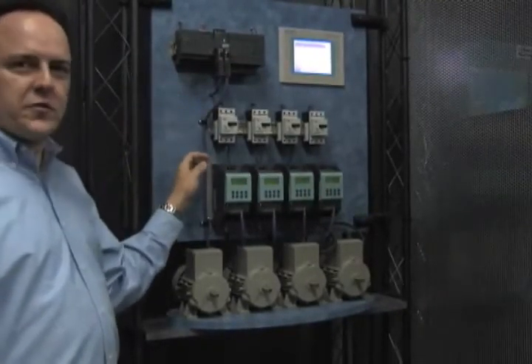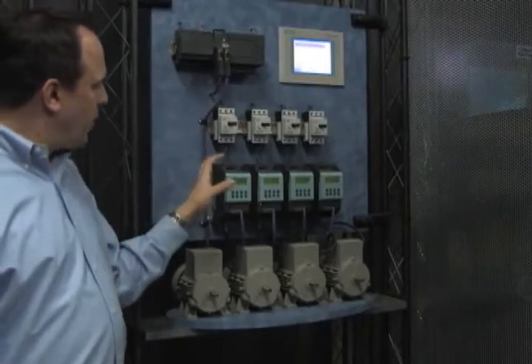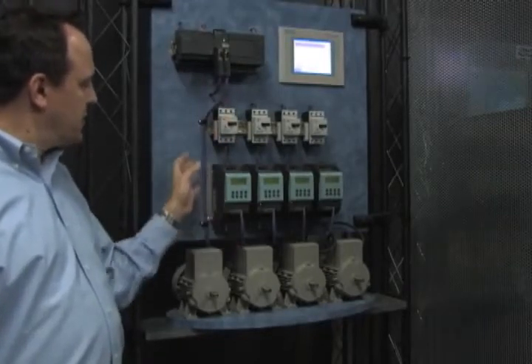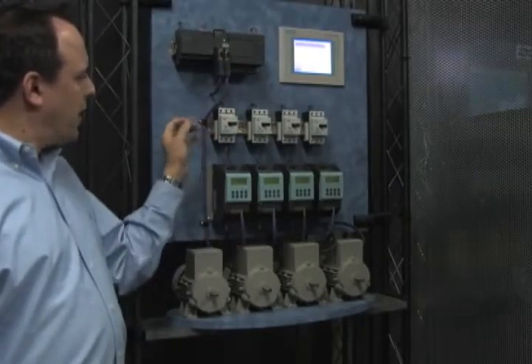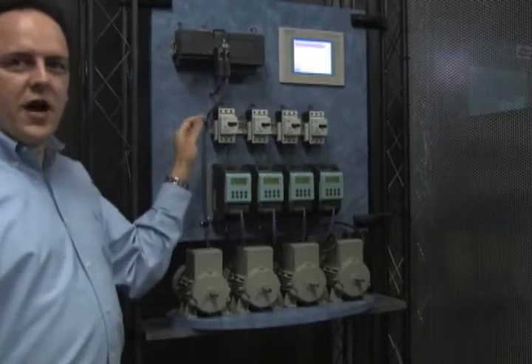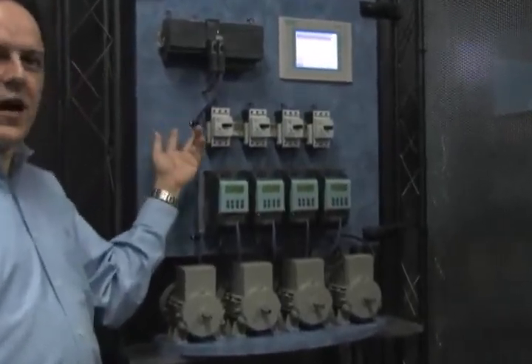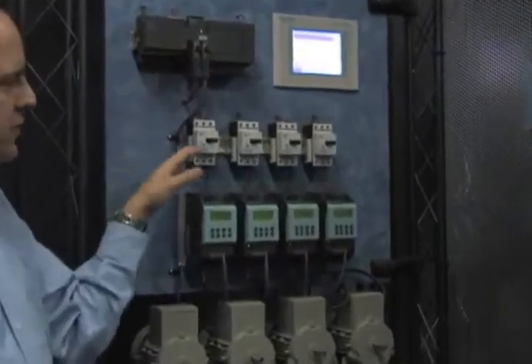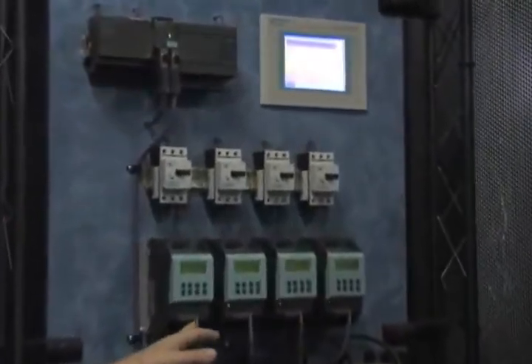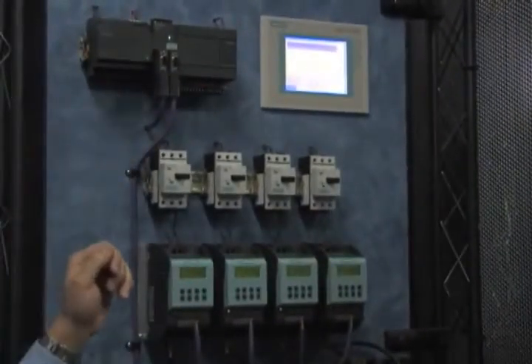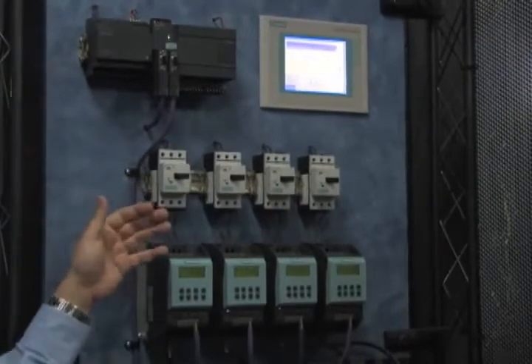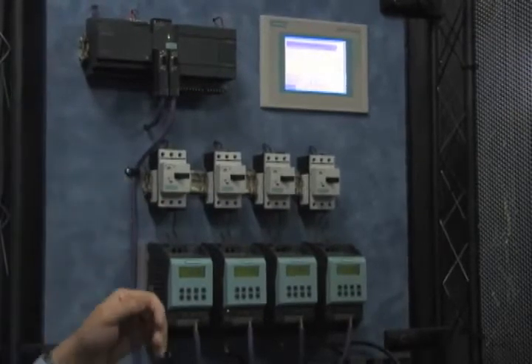It's done on an advanced communication system called USS protocol. Usually between a PLC and a drive, you'll have multiple wired signals for start, stop, reset, fault, and speed control. But here it's just done through two wires and configured easily in software, which saves a lot of money on manufacturing, wiring, and troubleshooting.